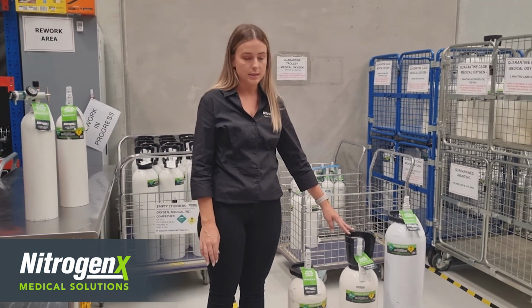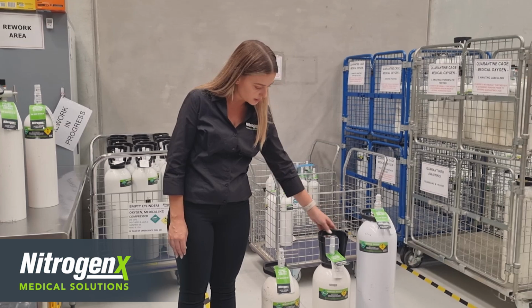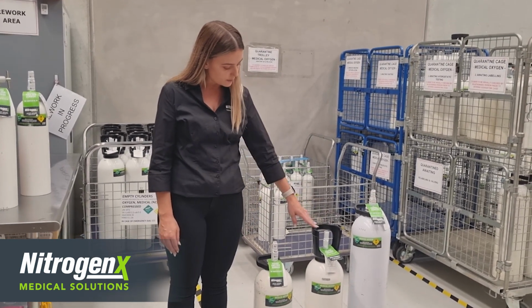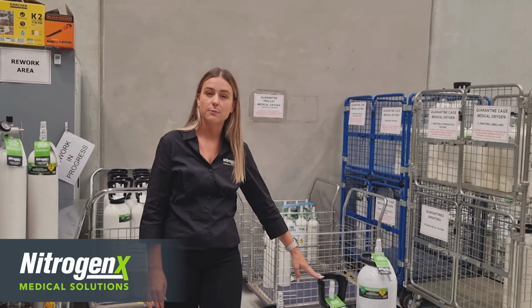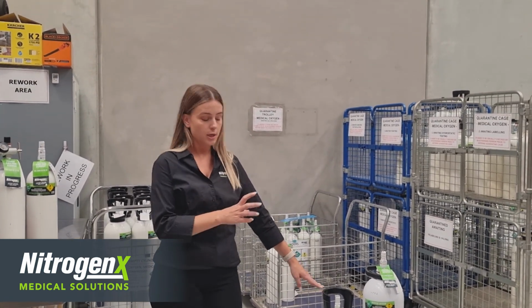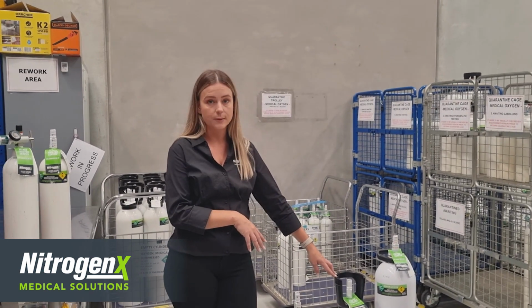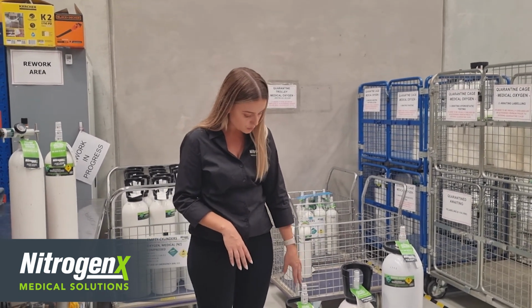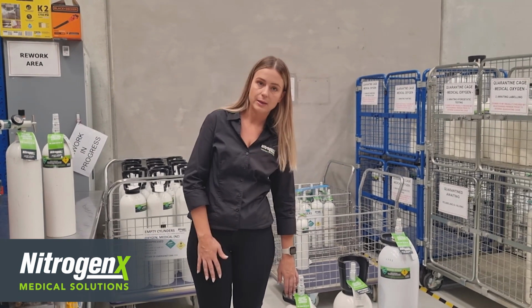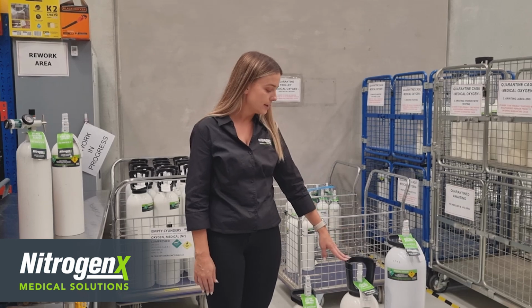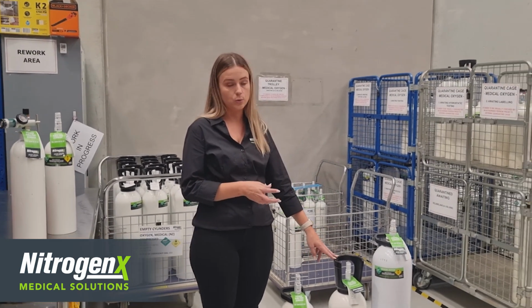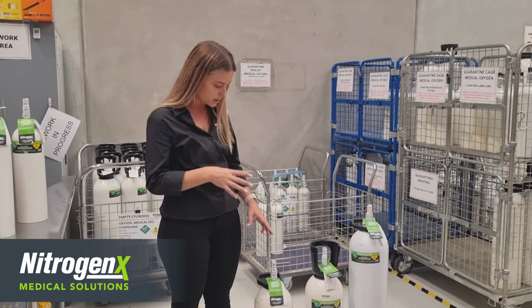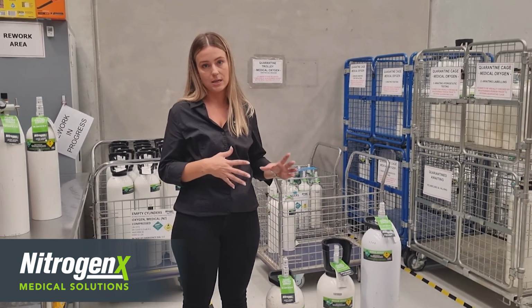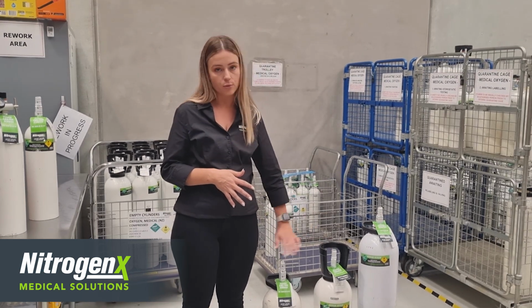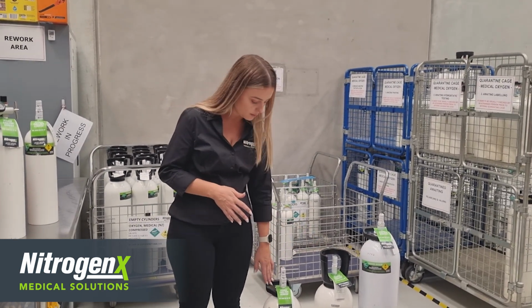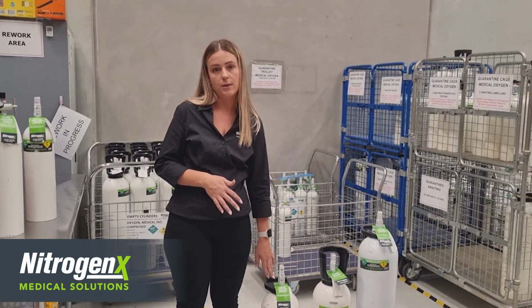Recently the medium cylinder has been updated to a new handle here. We have discovered that there is a certain type of regulator, the CAPES medical regulator, which is a bit too short to be compatible with this cylinder. That regulator is compatible with the old style, however these are being phased out. So if you are a customer who currently has one of the shorter CAPES medical regulators, then we would suggest changing to a standard size regulator so that you're able to use either of these cylinders quite easily. With these being phased out, stock may become an issue in the near future.